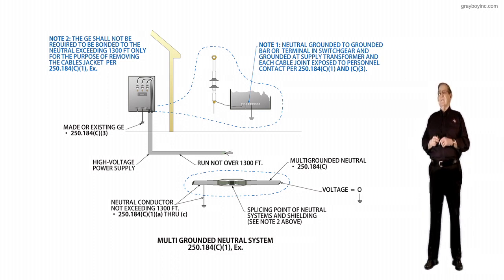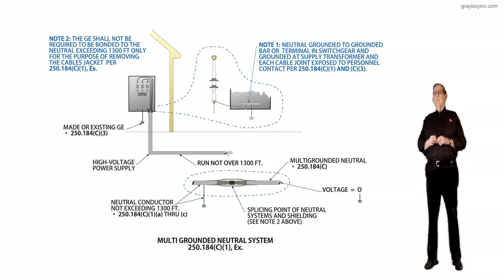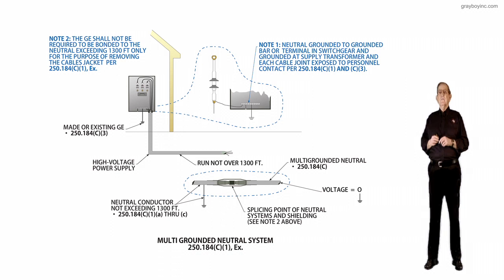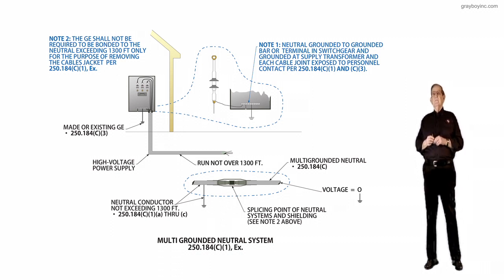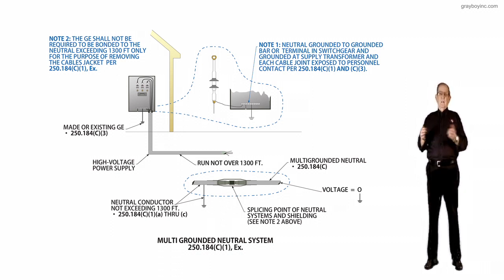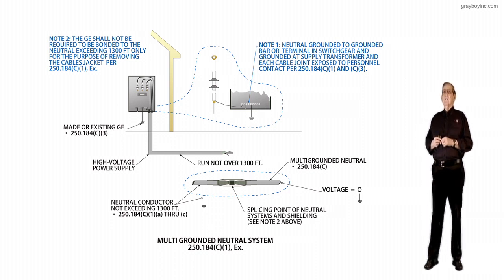A reminder: where insulation is not removed for splicing purposes, a ground is not required. We're just not making a splice. And I'd like to also remind that a power source can be PV, it can be wind, it can be fuel systems, and those are also outlined in 250.184(C)(1) exception. Now, the notes give us a little information.